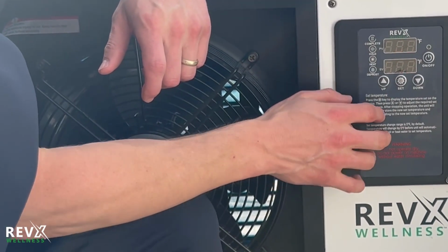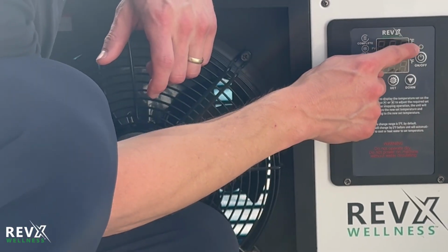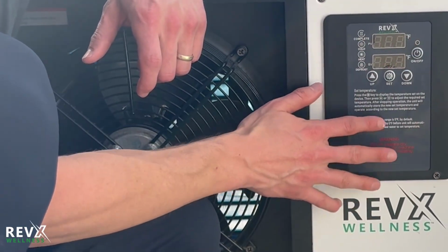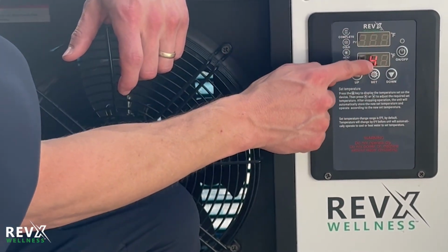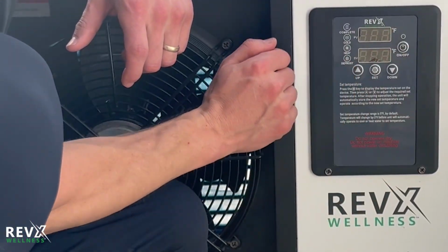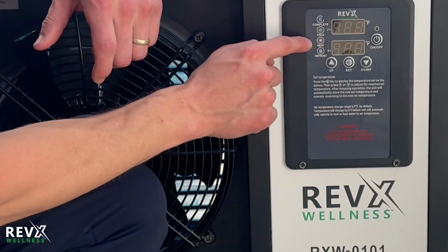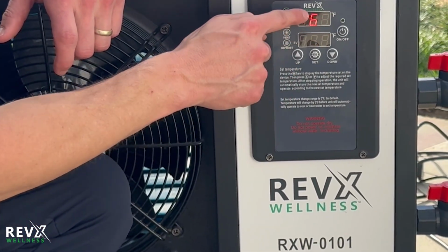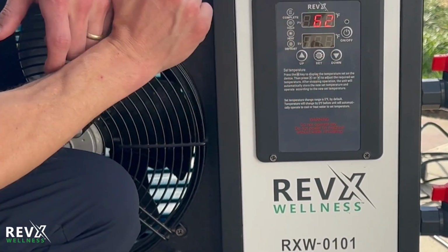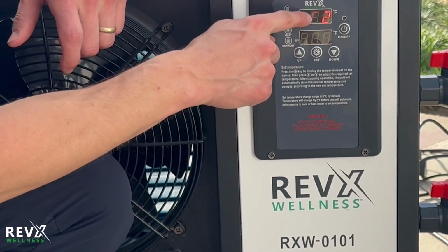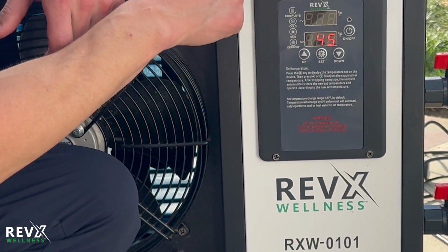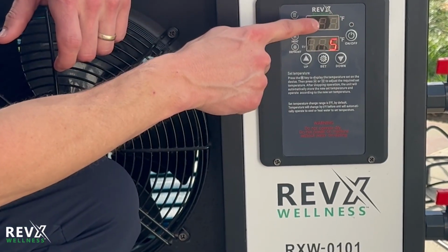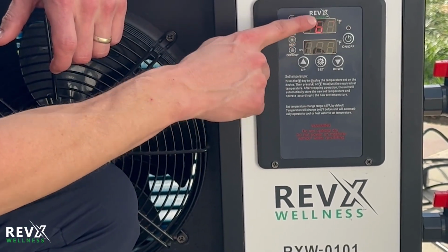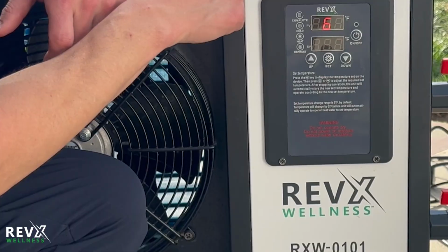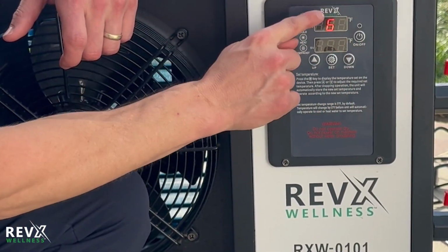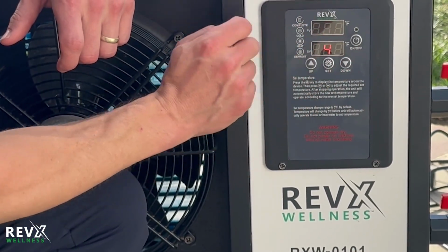This is the control panel. If the LED light is not illuminated, the chiller is technically off. Even though it's showing you the numbers, the chiller right now is off. The top number is the present value. This is the temperature that is inside the tub. Well, technically, it's the temperature that's inside the water tank, inside the chiller, which is 62 degrees. So this 62 degrees is what's inside the chiller, and the tub temperature is actually different by about 2 degrees.